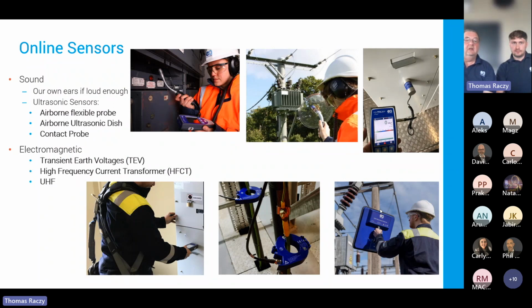We've got all the sound sensors, the external microphone, the parabolic dish, and the contact probe that we can all put into the handheld unit, and all of these will be generating phase reference or phase plots as long as you've locked onto the phase lock. We've got the other accessories shown at the bottom, which is obviously for your TEV sensors. You've got your actual handheld unit sensor, you've got your HFCT, and you've got your UHF directional arrow.